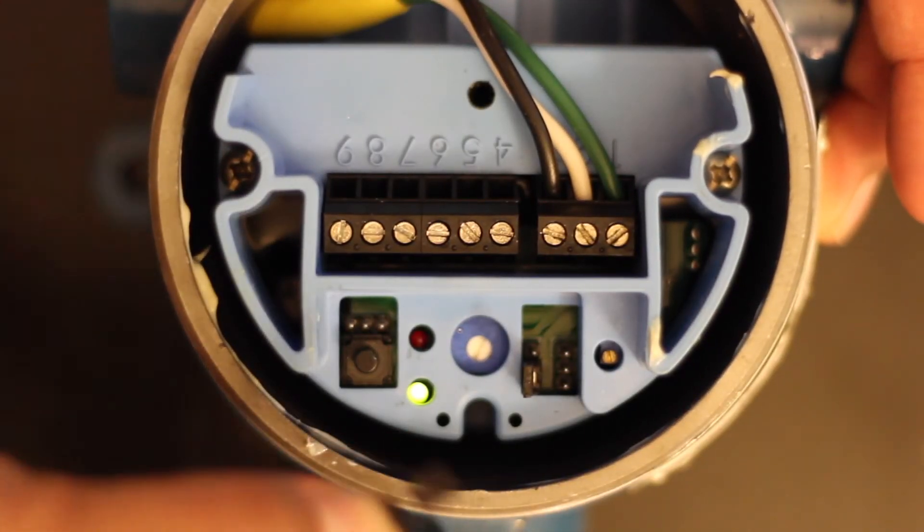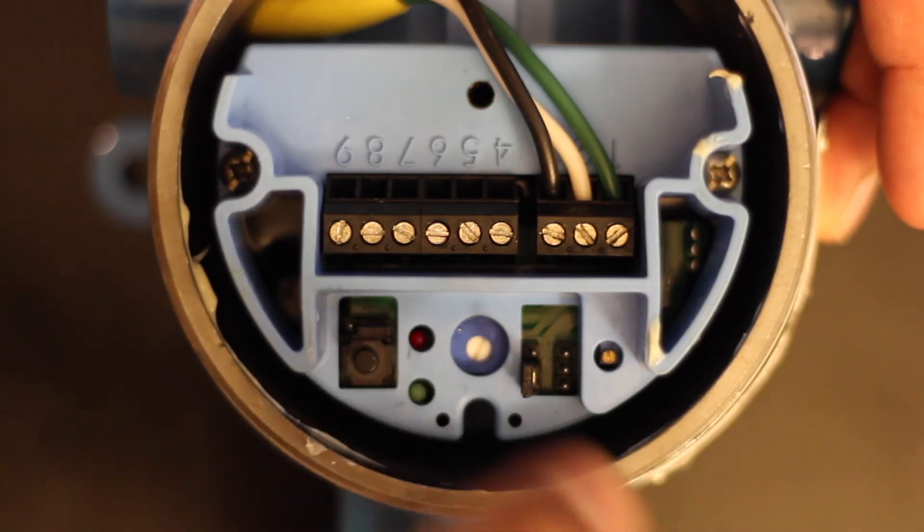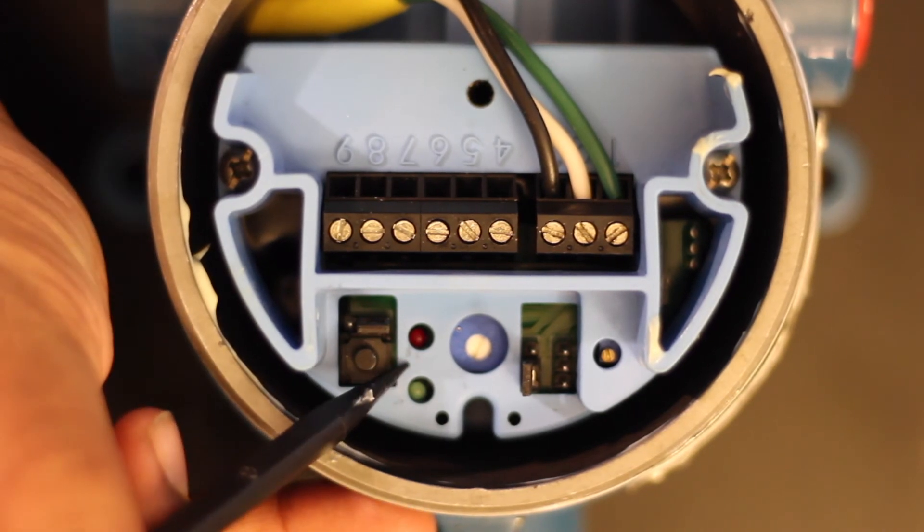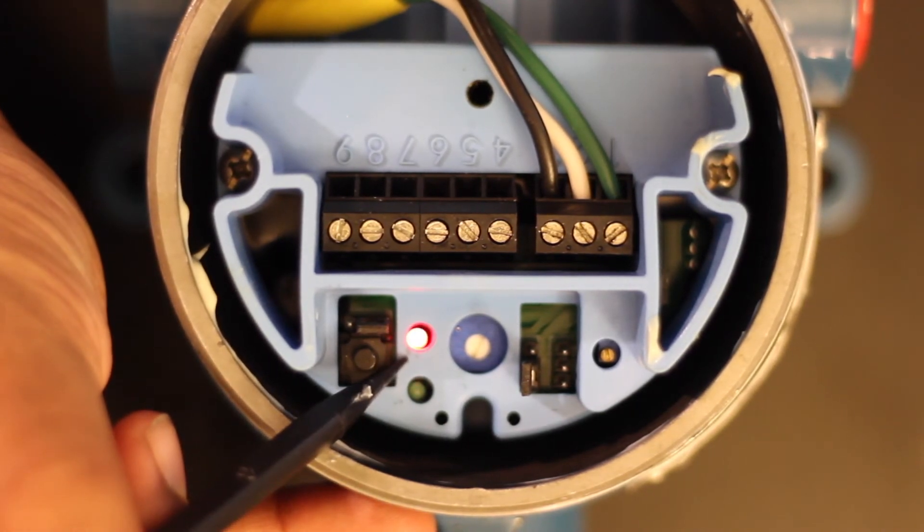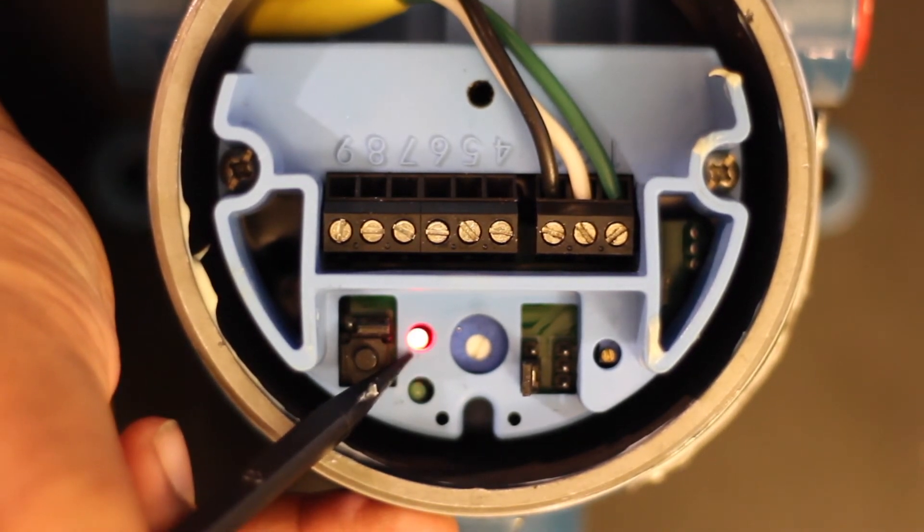Now we'll remove the time delay jumper. Place it on the first two pins closest to the red LED or pins number 1 and 2. The green LED goes out, and as you can see, the red LED flashes twice, pauses, and then flashes twice again. This indicates the mode, so this particular unit is in mode 2.